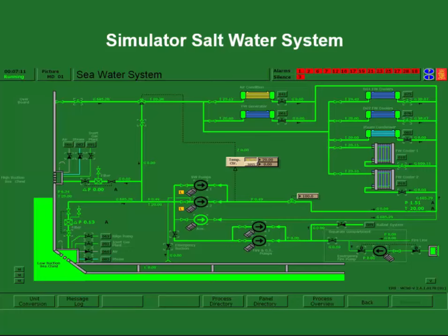One of the things I found is when the students are having a problem, say with overheating of a system, they will either put on 2 pumps or they'll put on 2 coolers. I'd never do that in real life. You've got to troubleshoot what the problem is.